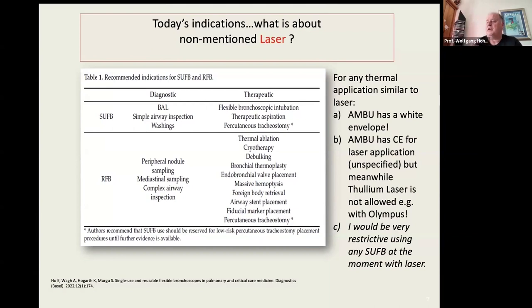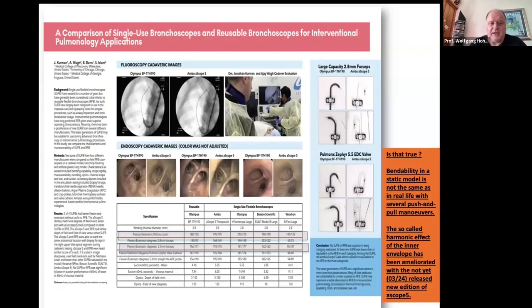There are comparisons between single-use and reusable scopes for interventional procedures, including well-known bending and de-bending tests with devices in the working channel. The inner sheath of a Vathin scope is completely different from that of an Ambu scope, so the actual working resistance differs significantly. For example, coated forceps such as Boston forceps (with a blue coat in Germany) versus uncoated Olympus forceps produce very different resistance in the working channel — something that must be tested in reality rather than relying on published specifications alone.